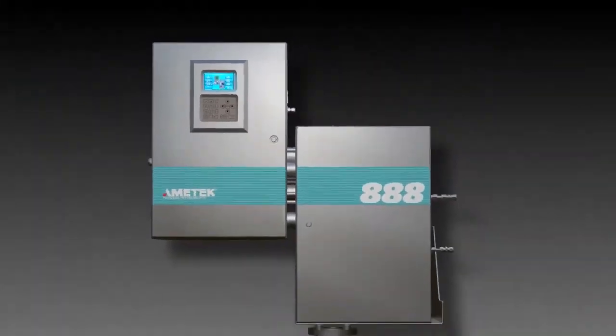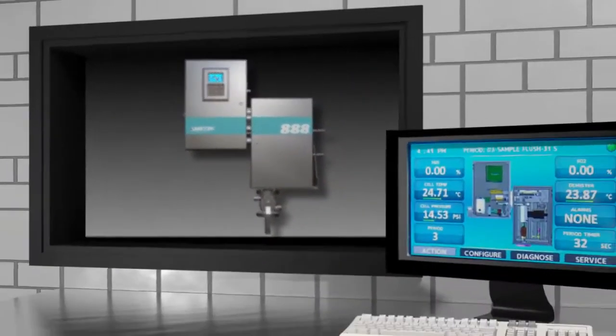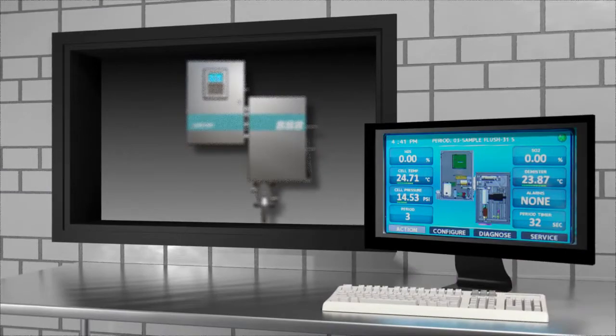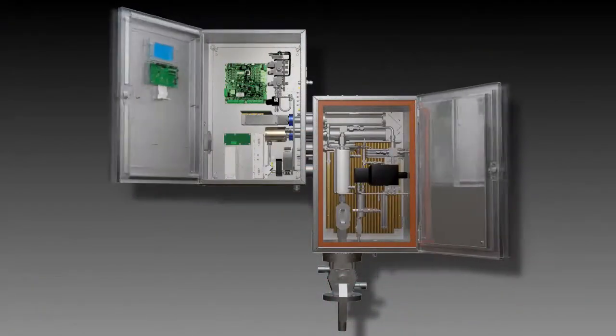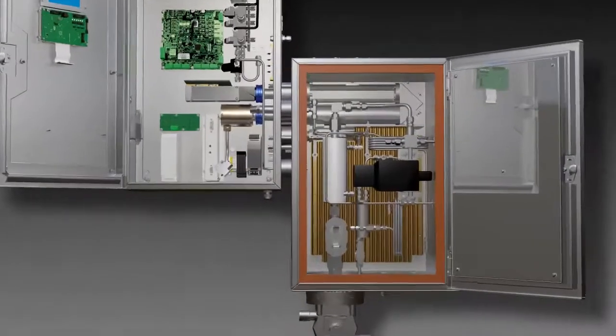The results are then transmitted to the distributed control system via built-in Ethernet and Modbus digital connections. The Model 888 addresses the most common external failure modes of previous generation analyzers: one being ingress of entrained sulfur liquid from the process, and the other being poor quality steam heating.